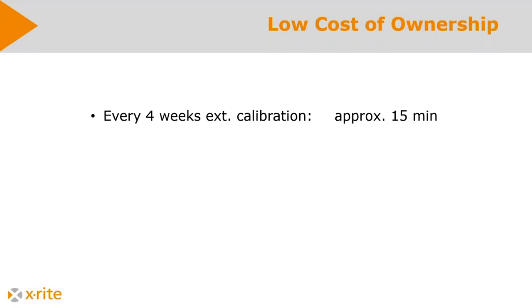Then we have a very low cost of ownership. What you should do is you should make an external calibration. This should be done every 4 weeks, and it takes approximately 15 minutes. The calibration itself takes only maybe 30 seconds, but okay, you have to pick up the standard, you have to go there, you have to place it, you have to press a button. So all in all, 15 minutes, this is not a lot. We recommend to have an annual maintenance, which is approximately 1,750 to 4,900 euros per year. It's an annual maintenance. It's also not that much.